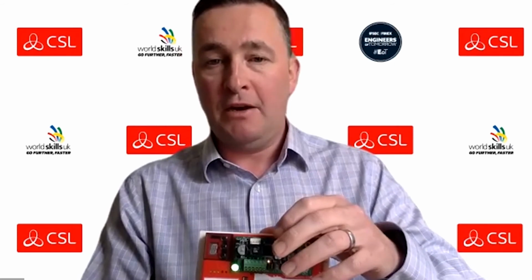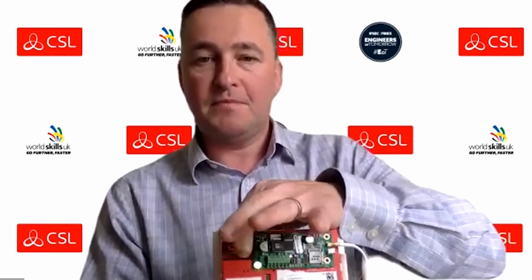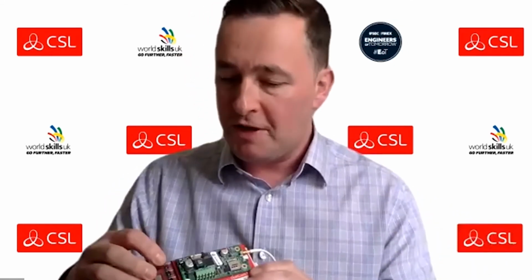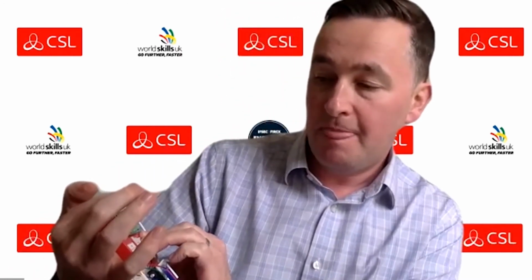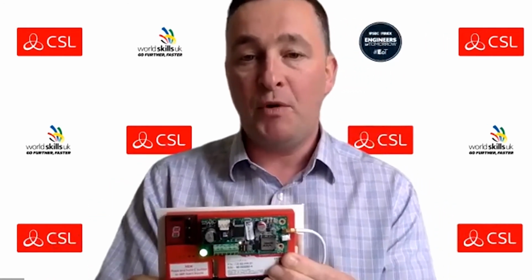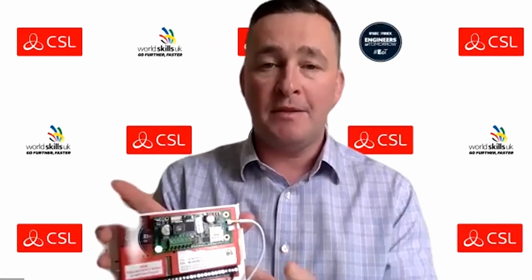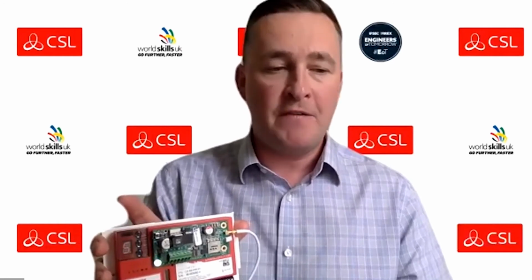And that would display learn OK. If you wanted to send test calls through to the monitoring station, then what you would do on here is you quite simply press A until S is displayed, and then press the C button, and that's it. And then what you'll see in the display is path test OK. So if you're going to be installing this just doing pins, then again, simple and straightforward. It's just a few button presses to get the device up and running.